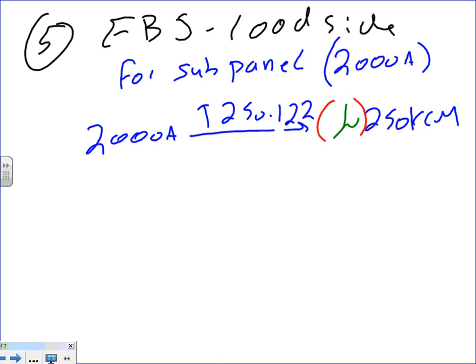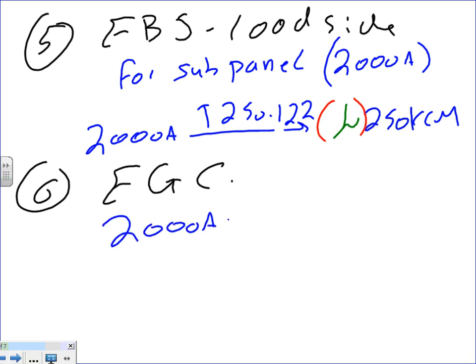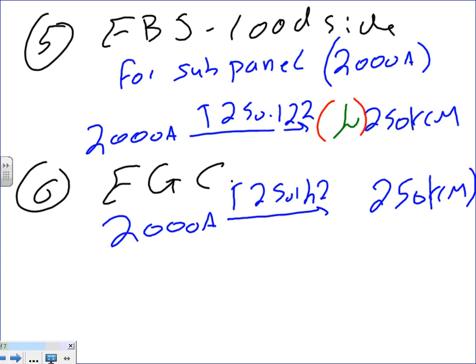Let me write number 6 right underneath it because they're very related. Number 6 is equipment grounding conductor. For equipment grounding conductor, the same calculation, guys. You take the 2000 amp, take it to table 250.122, and you end up with 250 kcm. Now, how many? Here's the question: how many?